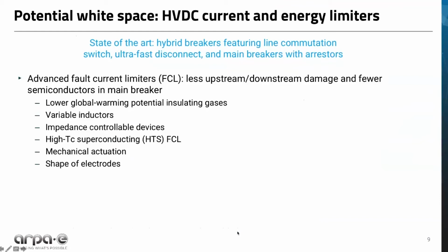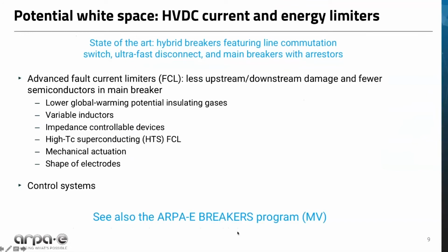There are different approaches to this. It could be lower global warming potential gases, like alternatives to SF6—something my colleague Isha Kizilai is particularly interested in. It could be variable inductors, impedance-controllable devices, high-temperature superconducting fault current limiters, which I'll talk about more in a moment when discussing superconducting systems, or mechanical actuation, different shaped electrodes, or control systems.